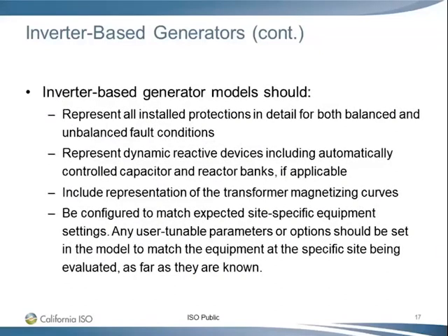Sometimes people don't pay much attention, but we do require you to represent all the protections in detail. So that's very important to us. So we know it will be tripped under certain conditions, and we can capture that in our study. Represent all the dynamic reactive devices, including automatically controlled capacitors and reactors, if applicable. Include representation of the transformer magnetizing curve, and then be configured to match the site-specific equipment setting. Next slide.